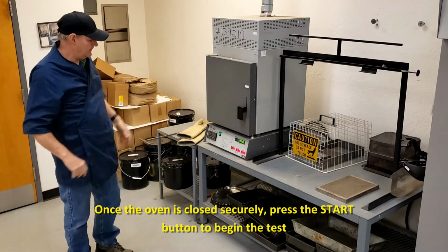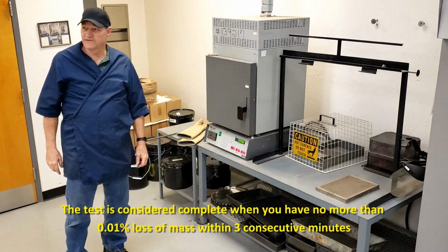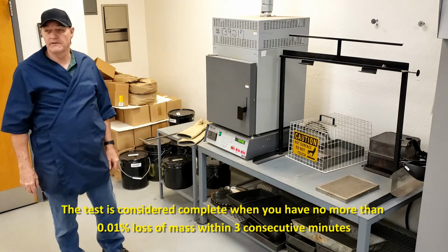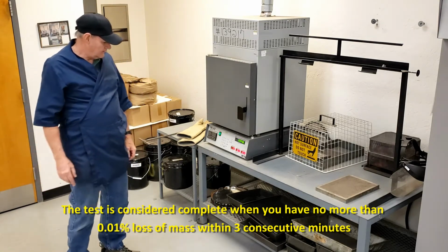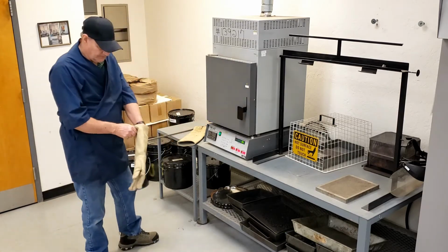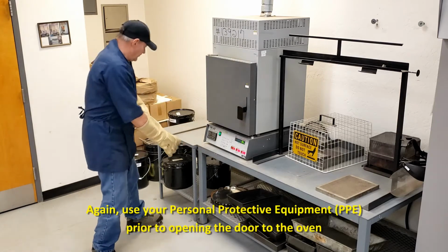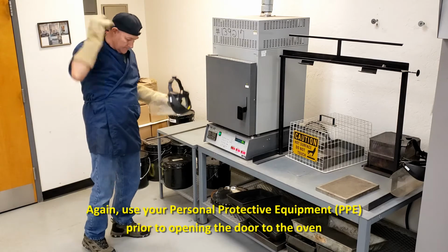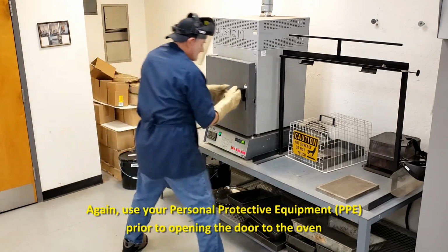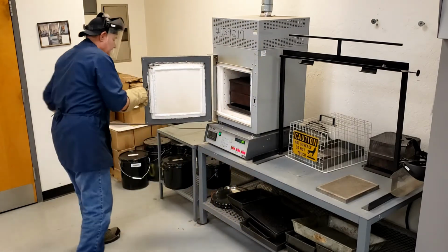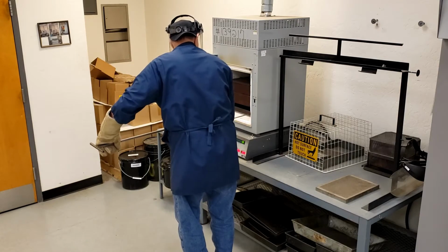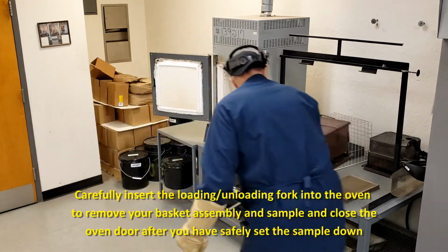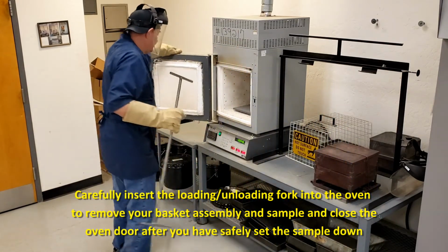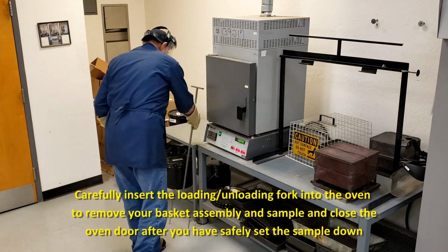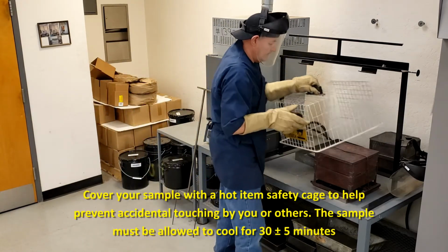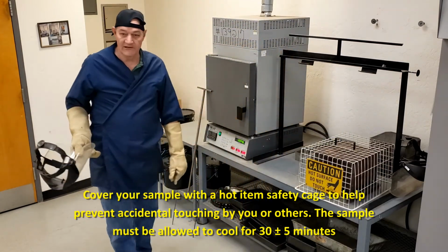You're going to let it burn until you have 3 consecutive minutes of mass loss of no more than 0.01%. That's when it's done. These machines, when it's done, it'll beep. Okay, it's completed. Again, make sure you wear your safety equipment. Make sure you cover it. And you're going to let it set for 30 minutes plus or minus 5 minutes.